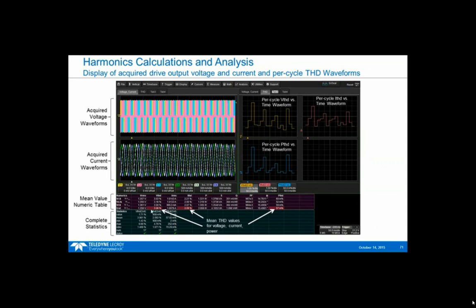And you can look and say, yeah, this drive looks pretty good. The voltage THD is 3%, the current THD is only 2%. That's not so bad, but when you look at the statistics and the waveforms, you can see there's some big variations. The peak voltage THD is almost 7%, just shy of 5% for current, and this might be a little higher. A lot of times there's a 5% limit for a lot of different applications, especially if you're plugging into the line or something like that.